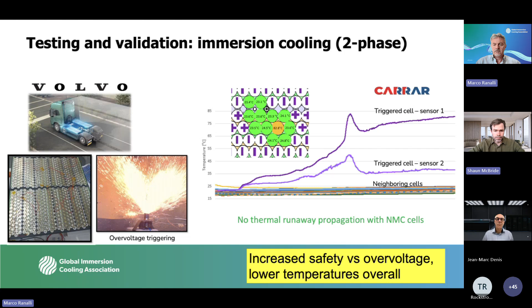And the third example, again, is in this case Shell and XOS. Here there was a test which directly compared a cold plate solution to an immersion cooled solution in an A/B comparison. And in this case, the cold plate solution failed the test, whereas in the immersion cooled solution, there was no thermal runaway propagation, even with large NMC cells.